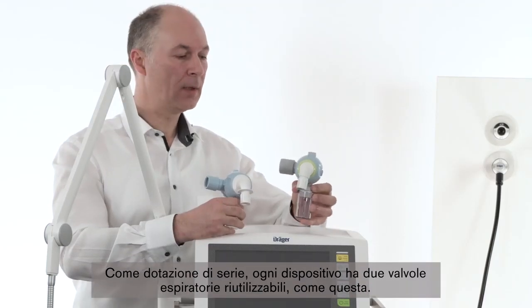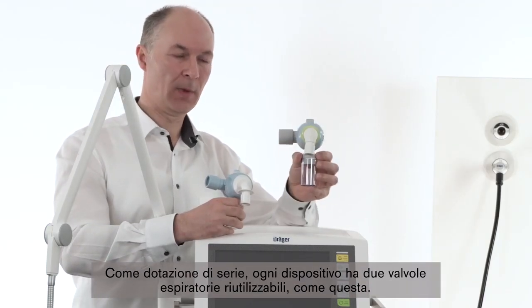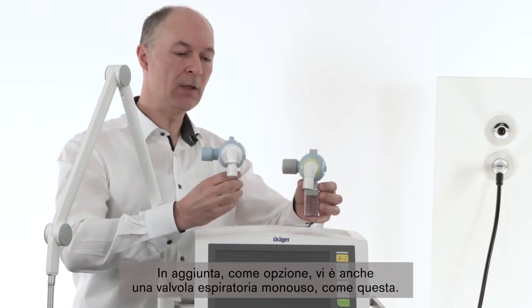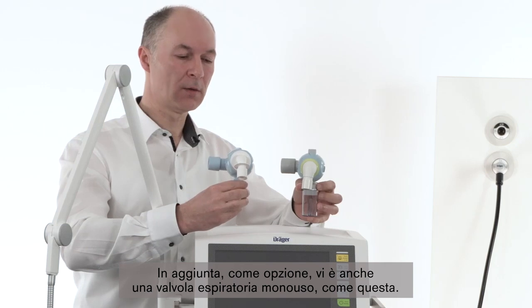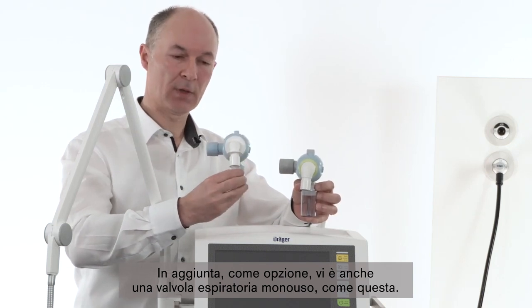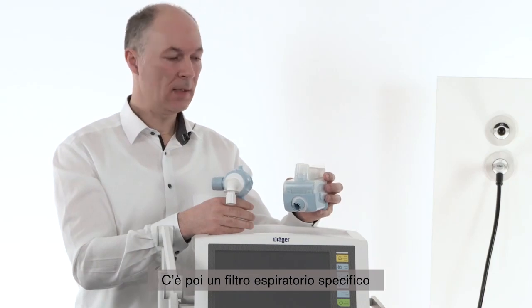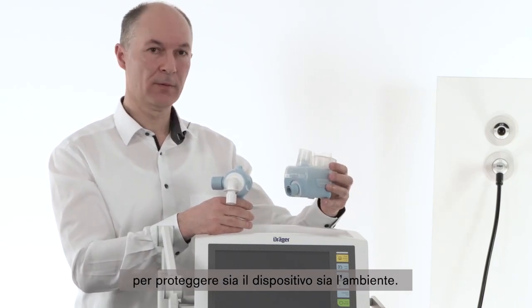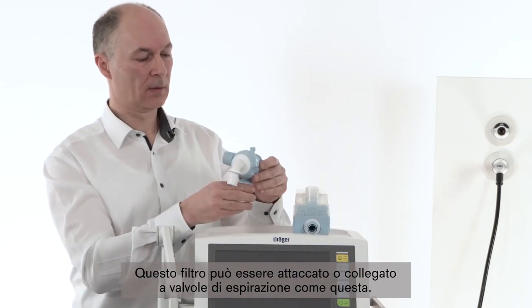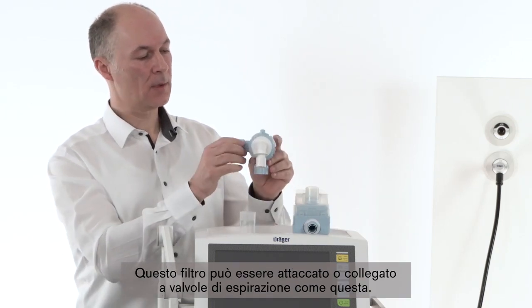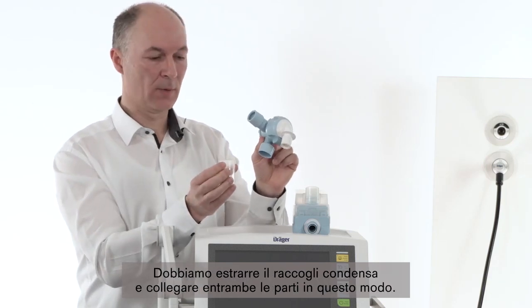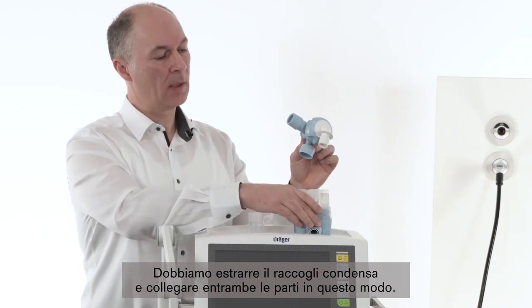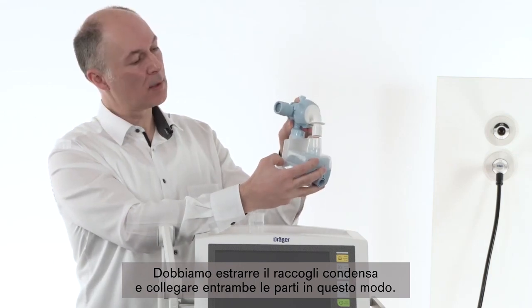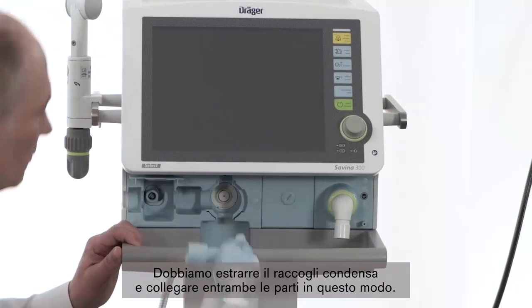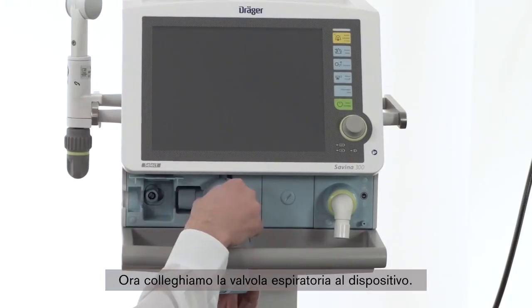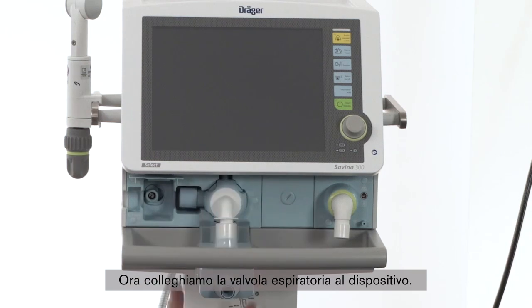As standard, every device is delivered with 2 reusable expiratory valves, which is this one. Additionally, as an option, you can also find a disposable expiratory valve, which is this. To protect the device and the environment, we have a specific expiratory filter. This filter can be attached to the expiratory valve like this. First, please remove the water trap and connect both pieces like this. Now we are attaching the expiratory valve to the device.